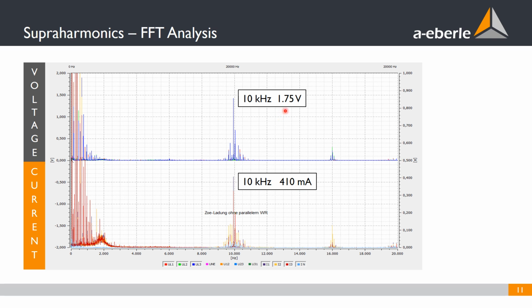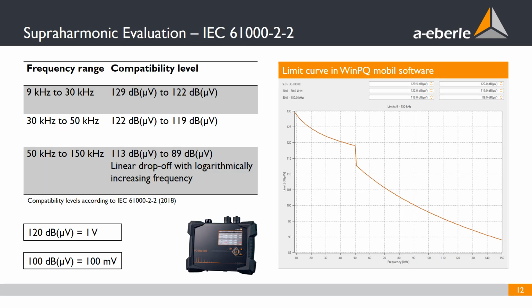Is it bad to have 1.75, or is it still below the limit of the grid? And in order to evaluate, it's not enough to do a snapshot measurement. You have to do a continuous measurement of at least 1 day or 1 week. And this is a big benefit of the PQ-Box-300, and I just want to show you some of the results here.